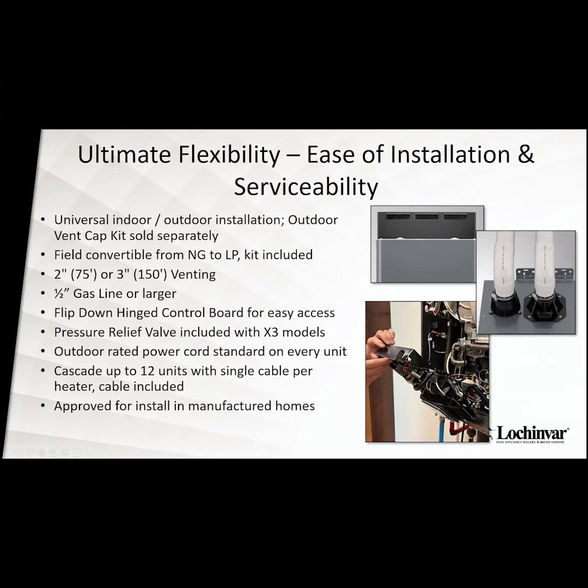The board that you see right here, there's one screw that removes that board, and then there's this little clip. You just push that down, and that whole board controller and everything is going to flip down. So you'll have access to the pump and to the gas valve right here. Right here is where you would change it to LP if you needed to. It's very built around serviceability. So if you did need to get in there, that whole board just flops right down, which makes it very, very easy to get in there.